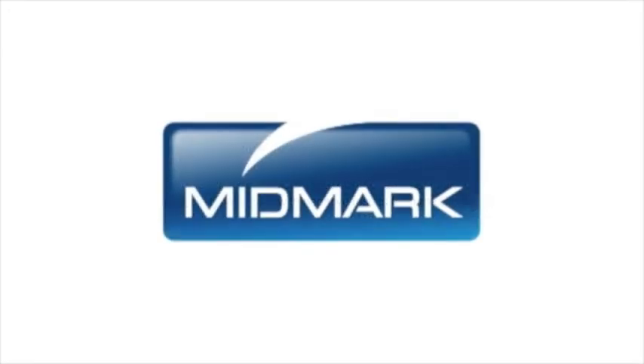After your sterilizer is installed, qualification testing using biological indicators should be performed prior to placing the sterilizer in service. 3 consecutive test runs for each cycle type tested, with negative results from the biological indicators, provide verification that the sterilizer has been properly installed. For more detailed information about installing your autoclave, please refer to the M9 M11 Installation and Operation Manual.